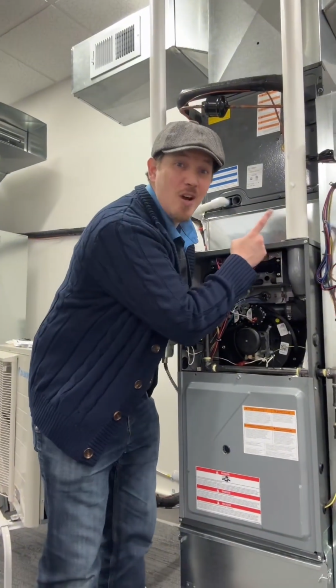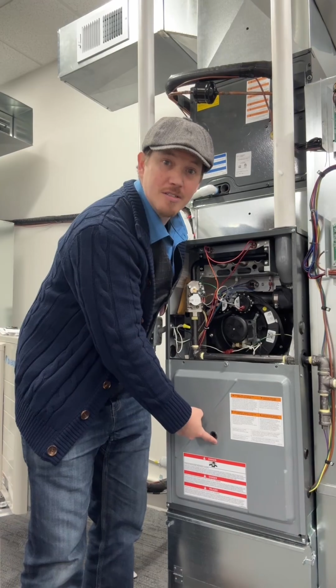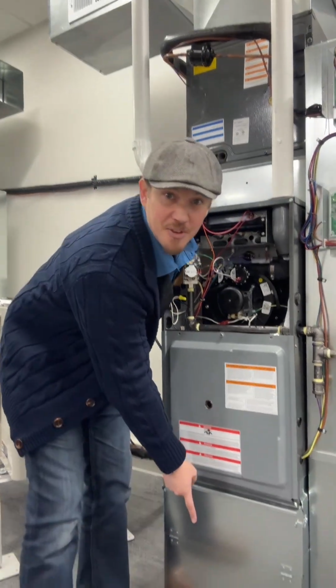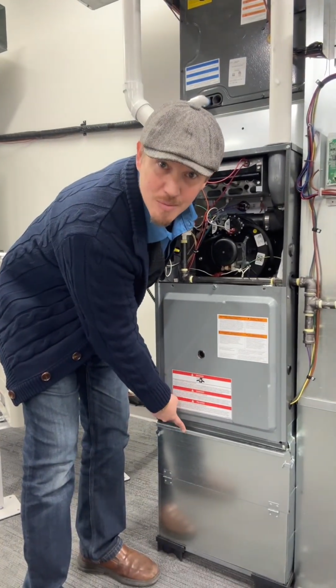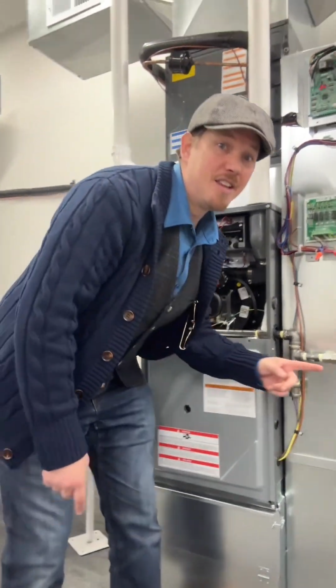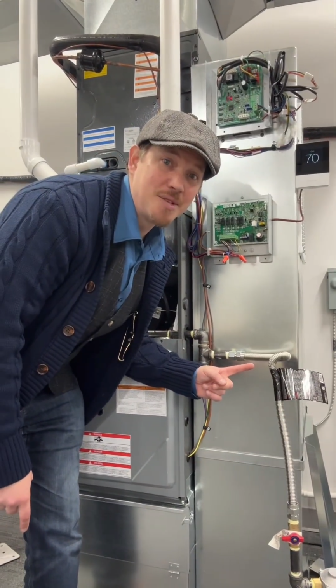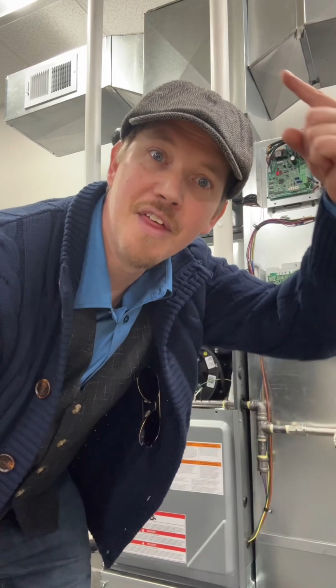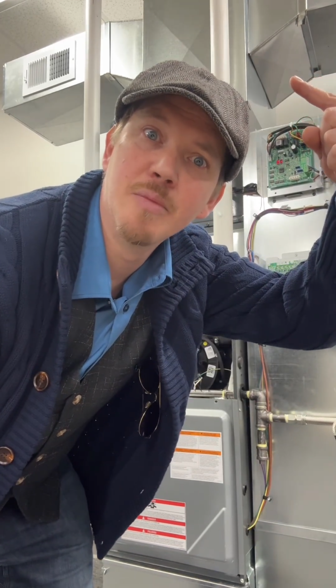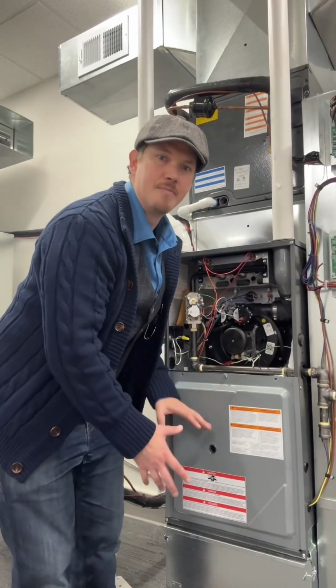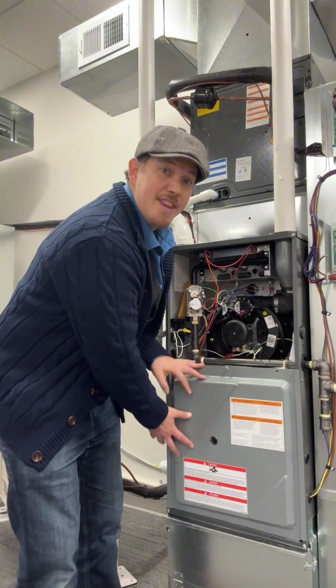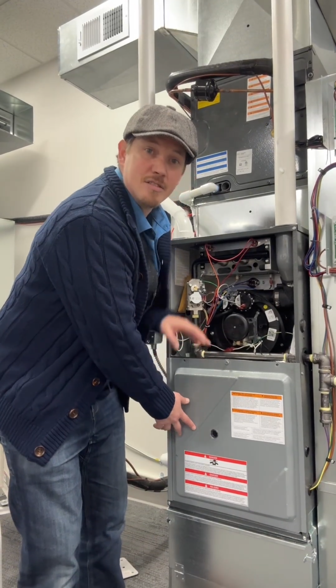When you're looking at these systems, there's total external static pressure. How much pressure is on this blower motor? This coil's adding pressure to this blower motor. This filter is adding pressure to this blower motor. This ductwork is adding pressure to this blower motor. That ductwork is adding pressure to this blower motor. It all adds up because this is internal.